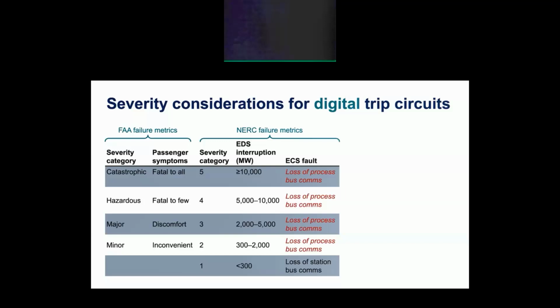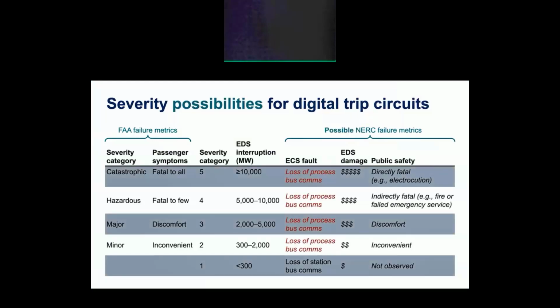We know from surveys that over half of the utilities in the United States are considering moving to digital trip circuits. Back in 2012, 670 million people in India, 10% of the world's population, lost power after a single piece of equipment failed. The blackout in 2003 in Italy was triggered by a single tree. The 1965 New England blackout was triggered by the failure of a single protective relay. And in 2016, about 20 million Kenyans experienced an outage triggered by a monkey. Single, simple failures must be isolated by trip circuits before triggering a chain reaction.